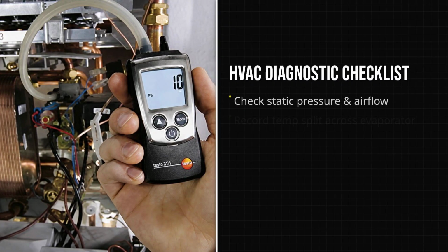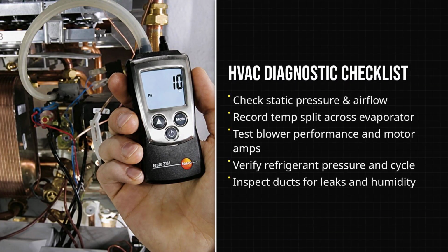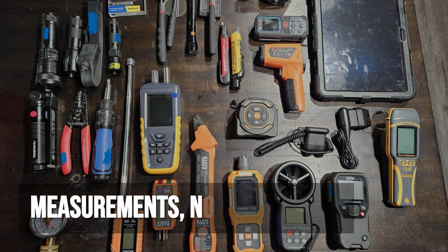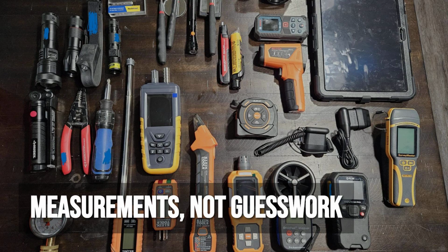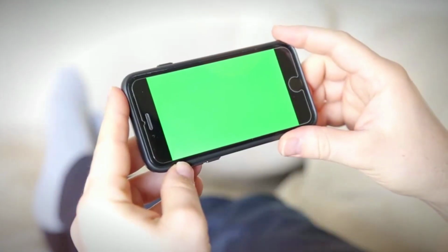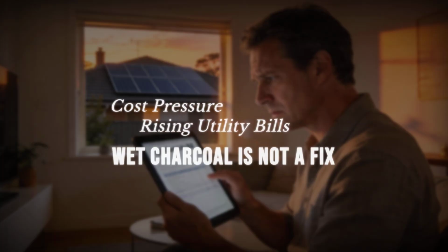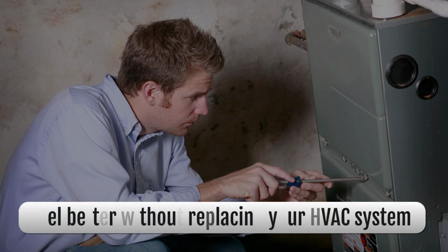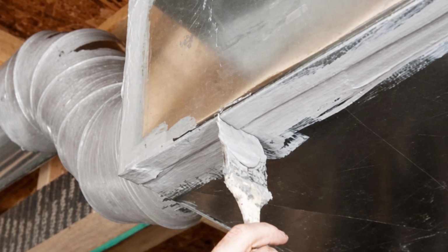A qualified technician can measure static pressure, temperature split, blower performance, refrigerant operation, duct leakage, and humidity. Those measurements tell us what the system is actually doing. We do not have to guess. I understand why homemade solutions are appealing. HVAC repairs can be expensive. Electric bills are rising. People want a simple way to make one uncomfortable room feel better without replacing an entire system. And sometimes a low-cost improvement really does help.